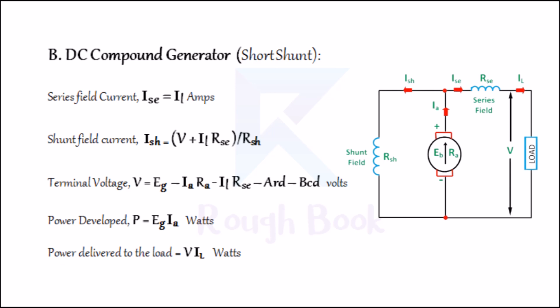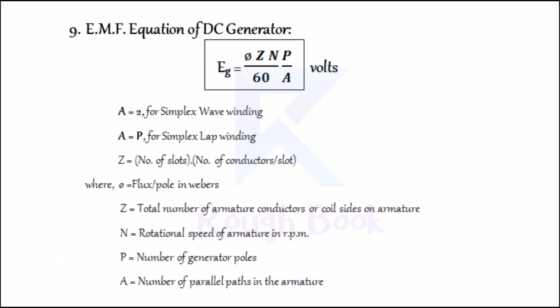Number nine: EMF equation of DC generator, given by EG = (φ × Z × N / 60) × (P / A) in volts, where A = 2 for simplex wave winding and A = P for simplex lap winding. Z = number of slots × number of conductors per slot. φ is the flux per pole in Webers. Z is the total number of armature conductors or coil sides on armature. N is the rotational speed of armature in RPM. P is the number of generator poles. A is the number of parallel paths in the armature, and E is the EMF induced in a parallel path in the armature.